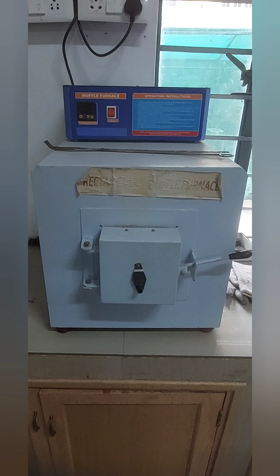This is called the muffle furnace, the instrument that we use to determine the ash content of the sample. We just turn the power on and set the required temperature, and there is an inlet to place the samples inside it. We place the samples over here, close it, and leave it for the desired amount of time. This is called the crucible, the sample holder for this instrument.